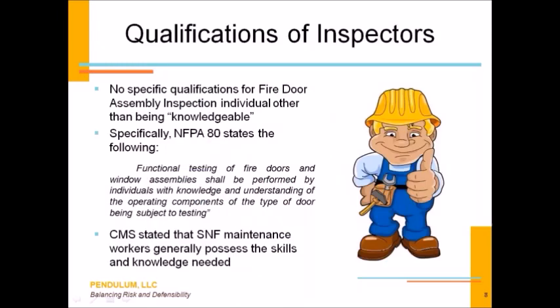Here's some good news, especially for our folks in the skilled nursing facility world, where you've got limited budget, limited capabilities, limited staff. CMS has come out and said, you know what, your maintenance staff generally possesses the skill and the knowledge needed to perform this function during the course of routine maintenance. NFPA 80 itself doesn't really prescribe any certifications or specific requirements, other than saying that the person performing needs to be qualified and have good knowledge of how a door and all the associated elements, the hardware, the frame, all the other components generally operate. So you've got to do this on an annual basis, and you've got to make sure that you're documenting this process.